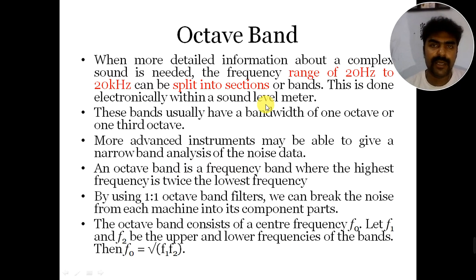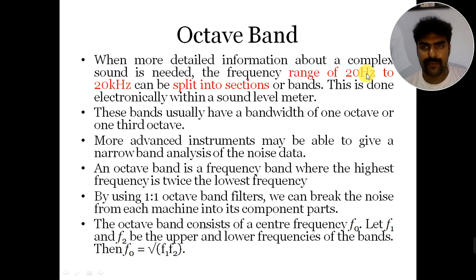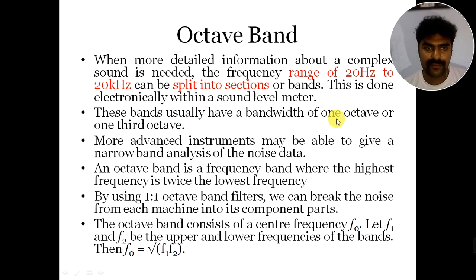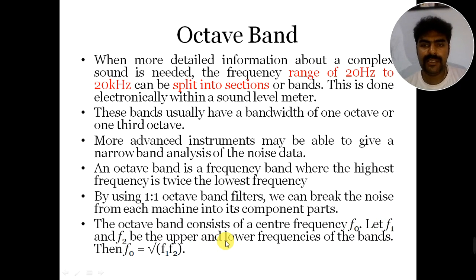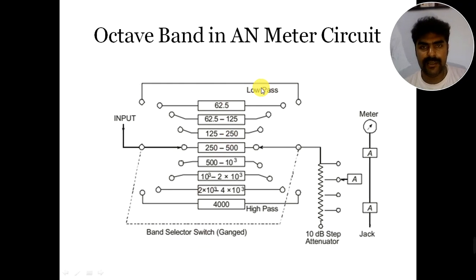The octave band filter is another component of the measurement circuit. Whenever more complex information is needed, the frequency range from 20 Hz to 20 kHz can be split into several sections or bands. This is done with an electronic circuit within a sound level meter. These bands have a bandwidth of one octave or one-third octave. An octave band is a frequency band where the highest frequency is twice the lowest frequency. The octave band consists of a center frequency F0, where F0 = √(F1 × F2), with F1 and F2 being the upper and lower frequencies of the band.